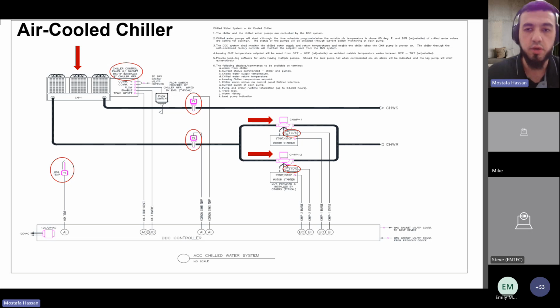Well, this is what's available, and I'll read some of them for you guys. Those points include an alarm from the chiller, which will come directly from the interface. It will tell us whether the chiller is operating or at fault. There's something going on, it's not working. You have the current status, so are the pumps on or off? You want to know that status at the operating workstation, and what will provide that is the current switch at each pump.